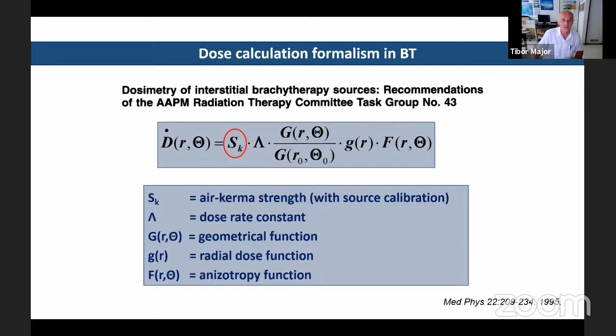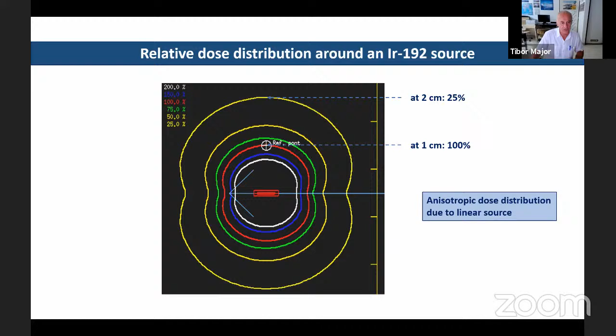And if we use this dose calculation formalism, we can calculate the dose distribution, what we can see here. In the middle, this is the small line source, and this is the relative dose distribution for the iridium-192. You can see the anisotropic dose distribution because of this linearity of the source. And if the relative dose is 100% at 1 centimeter here, and we increase the distance to 2 centimeters, the dose will be only 25%. So this is the consequence of the inverse square law. And this very nicely shows that close to the source, high dose can be delivered. And if we increase the distance from the source, the dose decreases very sharply.